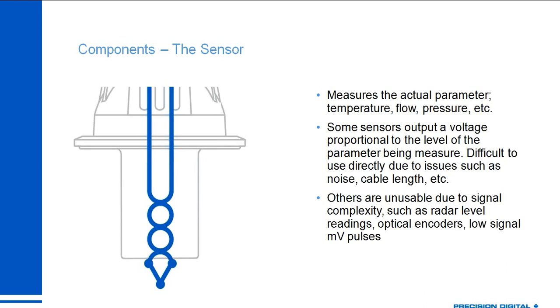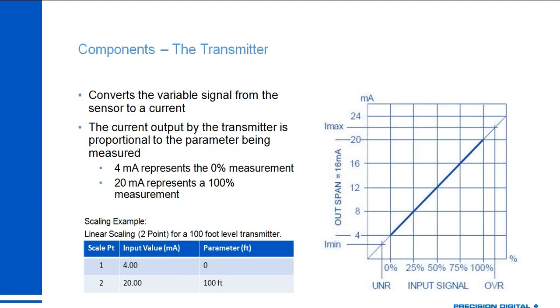Generally sensors output some kind of voltage, and you might consider using that voltage directly instead of a 4-20 loop — but there are issues. How far can it run before wire resistance becomes a problem? How affected will it be by noise? In some cases signals are so small and subject to outside interference that you couldn't do anything with them anyway. Systems such as radar level readings really need to be transmitted out as something else in order to be fully understood.